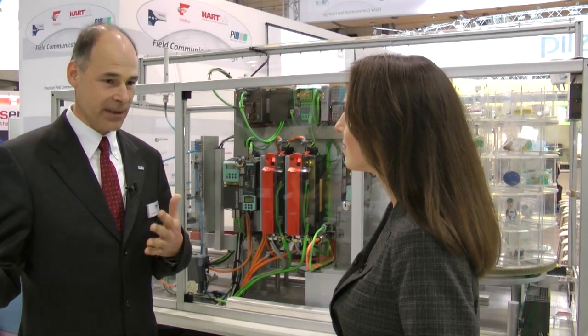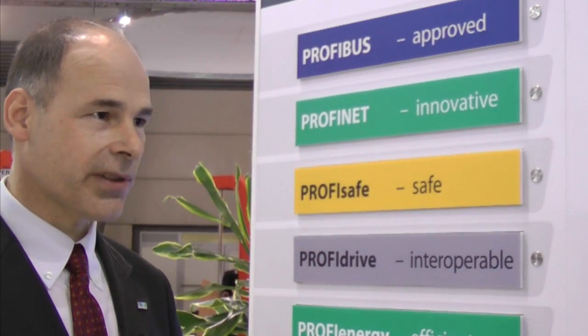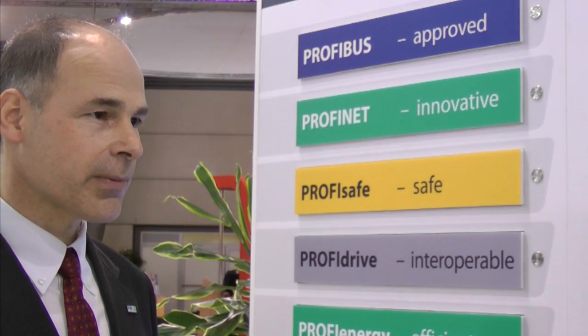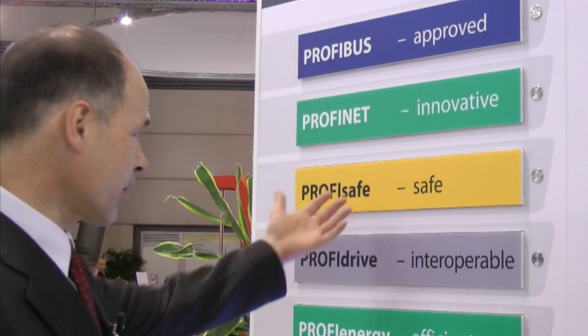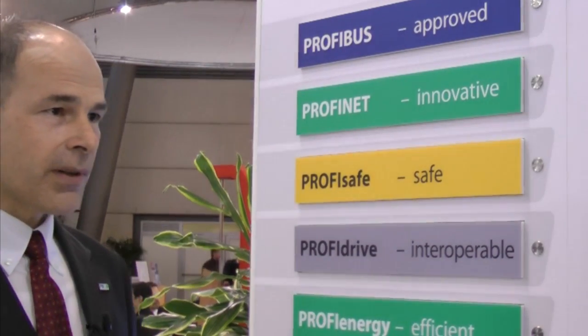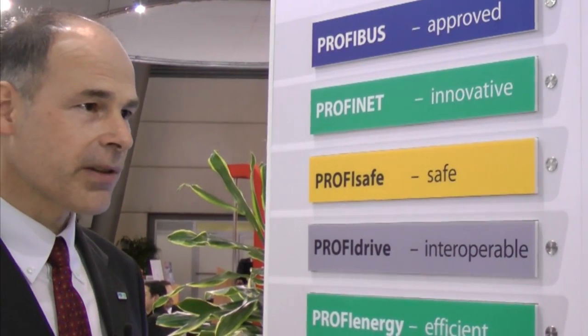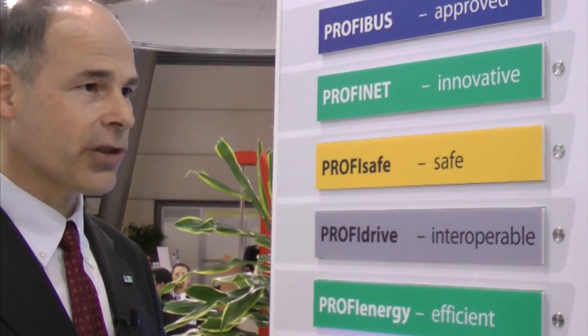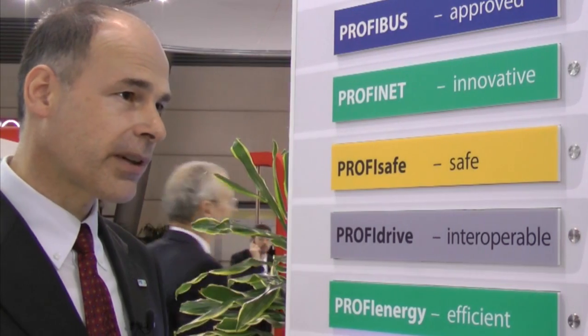And what are the consequences for the communication system? I would like to demonstrate this to you over here. A modern communication system in automation not only needs application profiles, but also appropriate auxiliary profiles, such as PROFISAFE or PROFIENERGY. Above all, the system must also be capable of several communication relationships from one device to multiple controllers — in other words, a shared device mode. And in addition, be capable of efficient support of hierarchical compositions — in other words, the iDevice functionality.